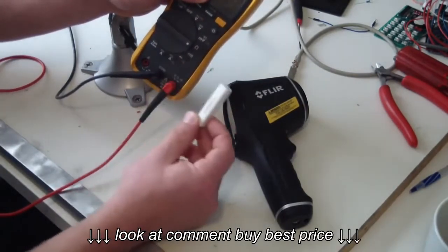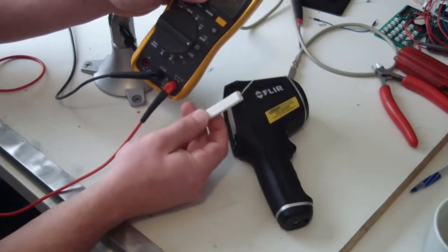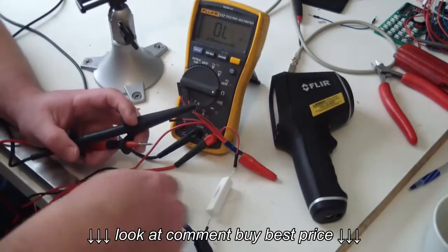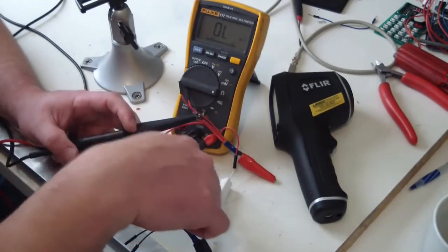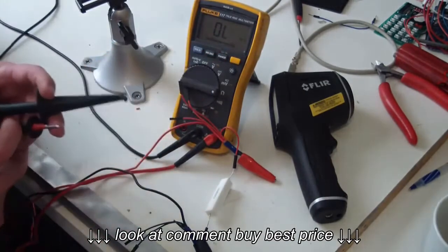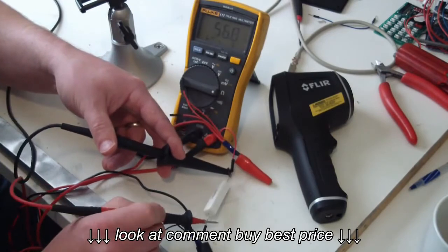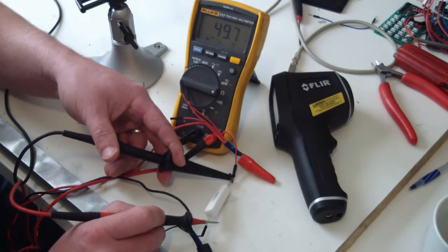So essentially, when you have a bad wire or a dirty connection, what you're adding is a big old resistor into the circuit. Here we have the wires of the circuit that we normally would have, and we've got a bad connection. Standing in for that is a resistor. And we've got our DMM set up here, and if we probe it, we can see it's 50 ohms. What happens if you probe a wire and there's no resistance, but there's still a problem? Because that happens all the time.